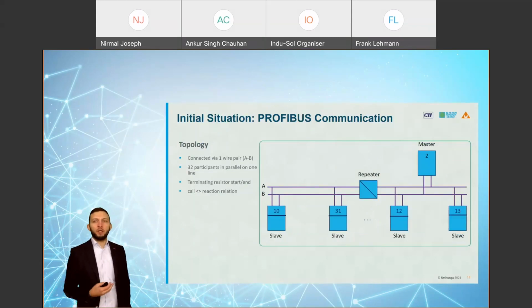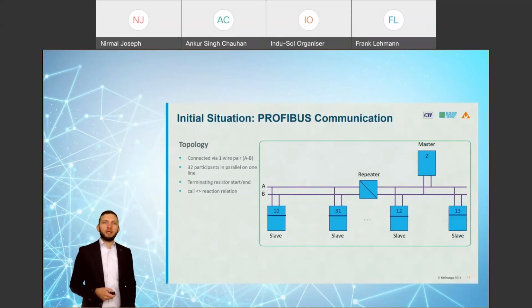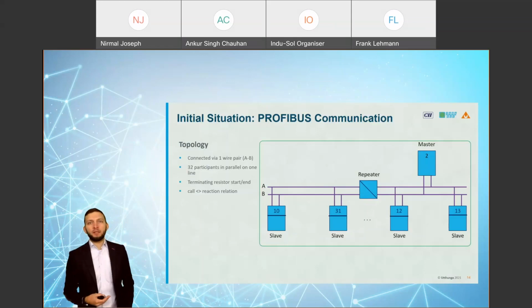First, our PROFIBUS system. For PROFIBUS we use a cable with 2 wires, giving us the possibility to send or receive information from the network. Basically we have 1 master in the network and some slaves, and the cyclic communication is based on master-slave communication. The master sends requests in the network, and the slaves have to respond back to the master.